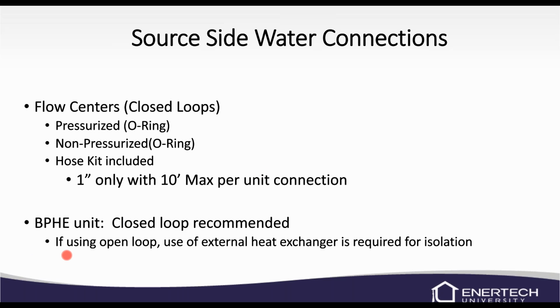If you've got an open loop, so you're doing like a pump and dump, you've got to use an external heat exchanger to isolate it from the unit. We cannot use open loop water on our braze plates. If you use open loop water on our braze plates, it will void the warranty on the unit. No open loop water. Those passageways through the braze plates are too small, and it'll collect sand and debris, and it'll plug it up and freeze it, and then you'll bust it, and then the whole unit's trash. So no open loop.